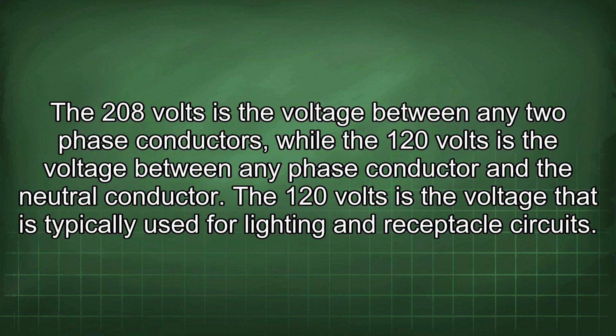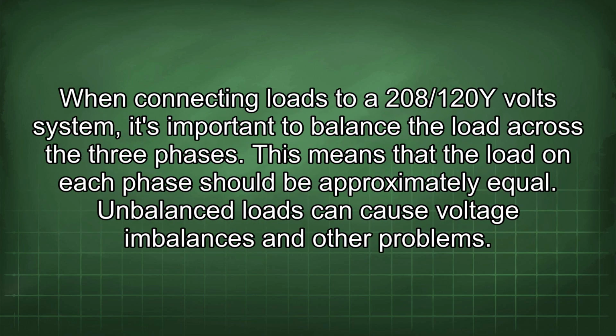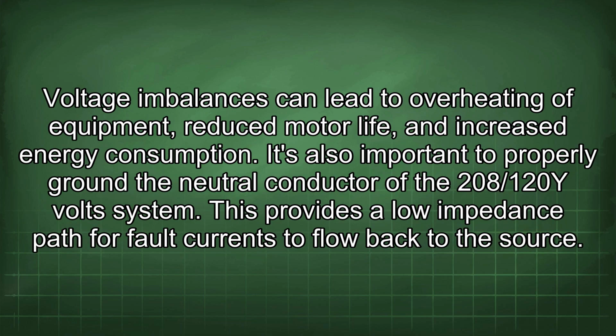The 208 volts is the voltage between any two phase conductors, while the 120 volts is the voltage between any phase conductor and the neutral conductor. The 120 volts is the voltage that is typically used for lighting and receptacle circuits. When connecting loads to a 208/120 volt system, it's important to balance the load across the three phases. This means that the load on each phase should be approximately equal. Unbalanced loads can cause voltage imbalances and other problems. Voltage imbalances can lead to overheating of equipment, reduced motor life, and increased energy consumption.